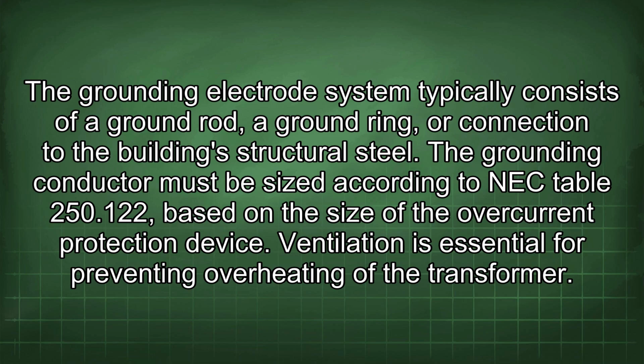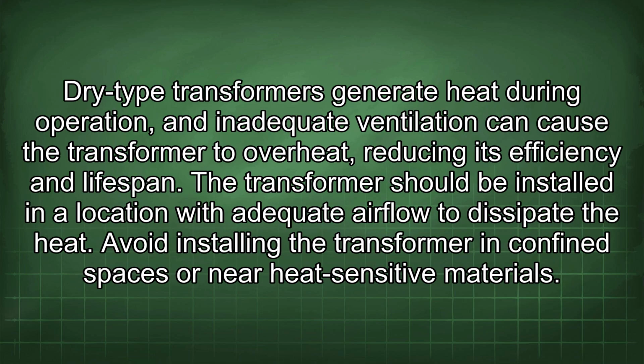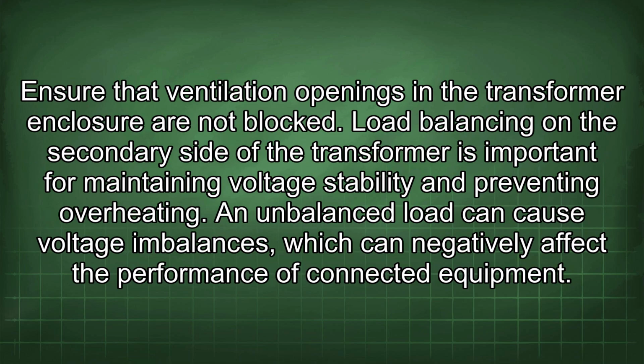Ventilation is essential for preventing overheating of the transformer. Dry-type transformers generate heat during operation, and inadequate ventilation can cause the transformer to overheat, reducing its efficiency and lifespan. The transformer should be installed in a location with adequate airflow to dissipate the heat. Avoid installing the transformer in confined spaces or near heat-sensitive materials. Ensure that ventilation openings in the transformer enclosure are not blocked.